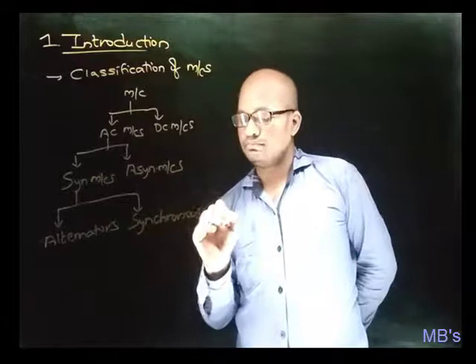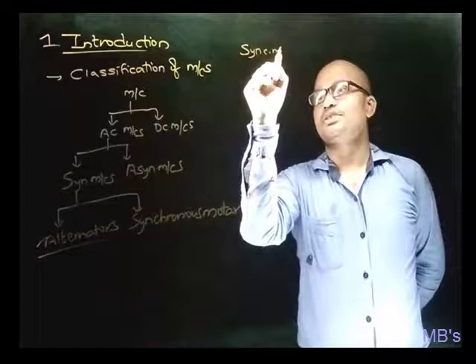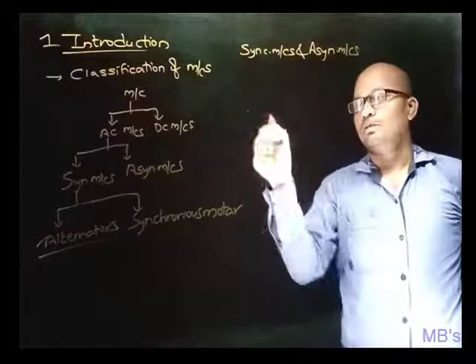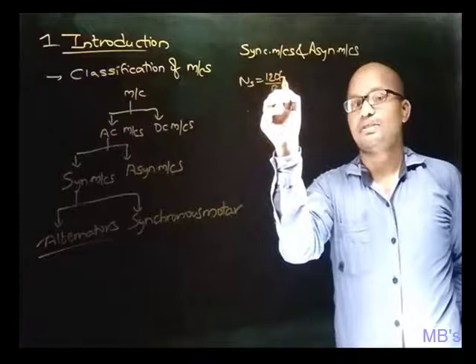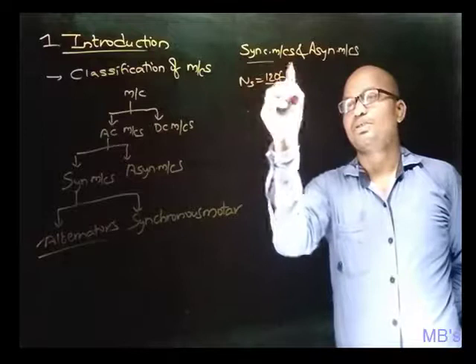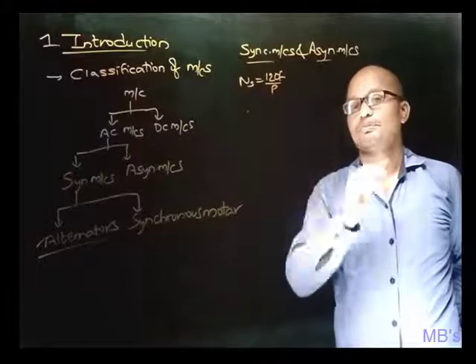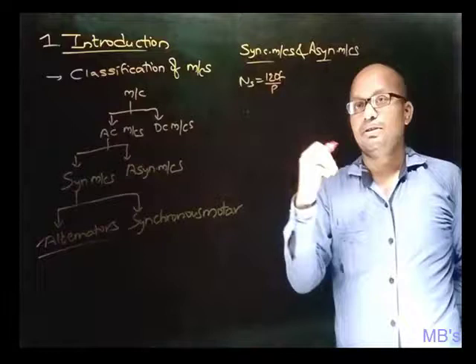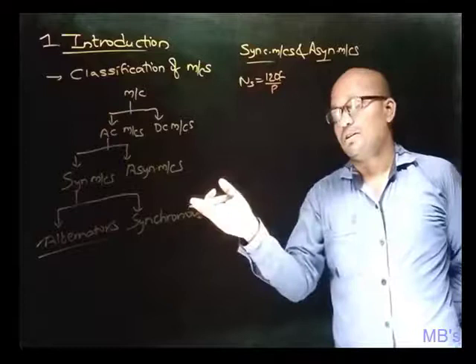Alternators are our focus. The synchronous speed Ns is given by 120f/P, where P is the number of poles and f is frequency. If a machine runs at this speed, it is called a synchronous machine; if it runs at any other speed, it is called an asynchronous machine. Examples of asynchronous machines are induction generators (which run above synchronous speed) and induction motors (which run below synchronous speed), whereas synchronous machines — alternators and synchronous motors — run exactly at synchronous speed.